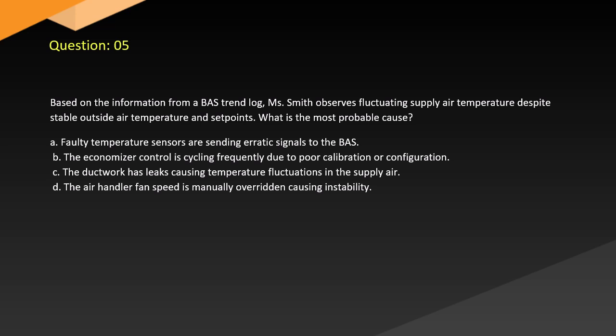A. Faulty temperature sensors are sending erratic signals to the BAS. B. The economizer control is cycling frequently due to poor calibration or configuration. C. The ductwork has leaks causing temperature fluctuations in the supply air. D. The air handler fan speed is manually overridden causing instability.